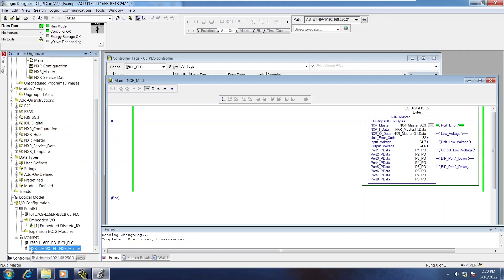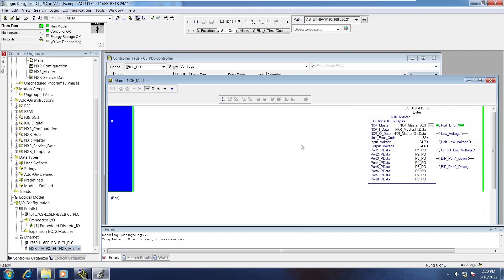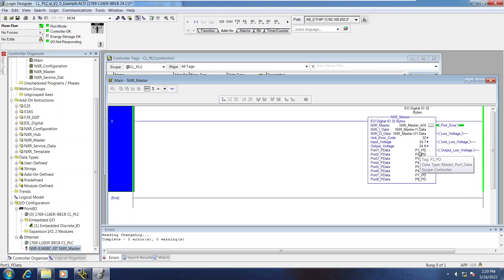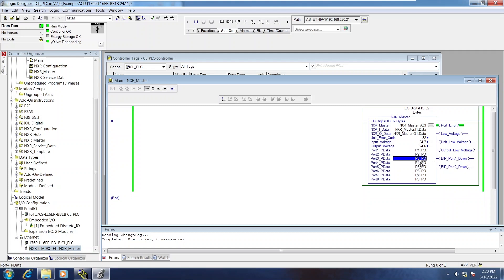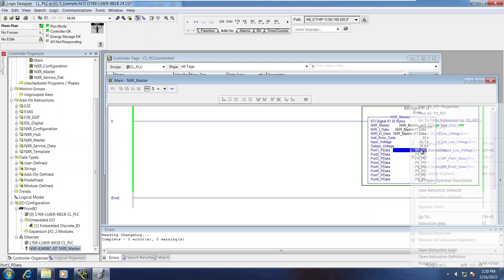There's also no exclamation mark or anything on the Ethernet device here. So what this AOI essentially does is displays everything that's pertinent to the base unit. So low voltage alarms, port down alarms, but it also breaks out all of the process data and relevant bits of information for all eight ports, and it groups them into eight port variables. That can be seen here.